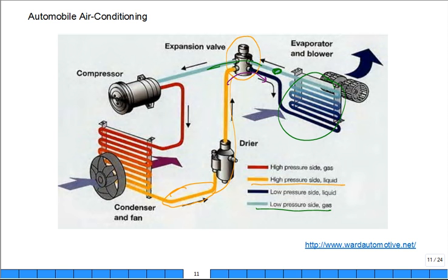It'll modulate the flow of the liquid into the evaporator. It'll control this flow rate by opening it or closing, pinching off. True? And so what happens is you don't want to overly flood the evaporator or starve the evaporator. You want to give it just the right amount based on the temperature coming out of the evaporator. So I pass that around.